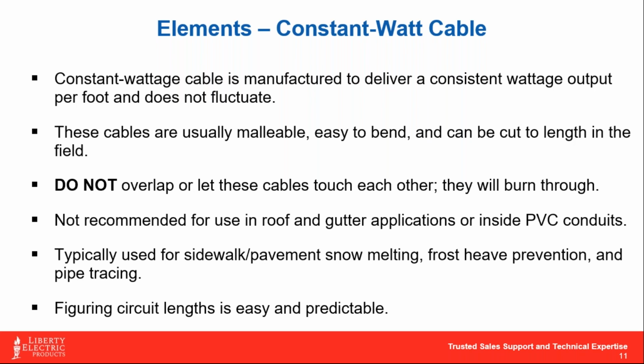However, the big drawback to these particular cables is that they cannot be allowed to touch against each other. There is no mechanism for these to back themselves down, and their output temperature is often far greater than the 150 F that a low temp self-regulating cable will give you. So finding a constant wattage cable rated for roof application, there isn't one that goes beyond, say, 6 watts a foot that I'm aware of in the industry.